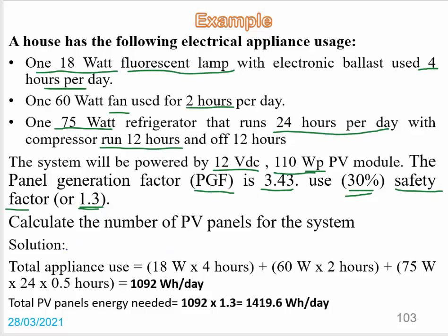The solution: total appliances use is 18W × 4h plus 60W × 2h plus 75W × 12h (the refrigerator runs with its compressor for only half of 24 hours, so we multiply by 0.5). The total result is 1092 watt-hours per day.